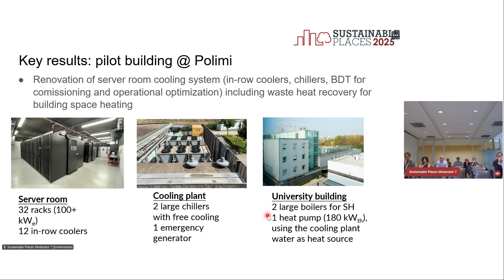Let's see if we can reduce it a little. So, in conclusion, we are optimizing the cooling system, doing different things. We are changing the so-called in-row coolers, a kind of fan coil used to cool down the room, with a higher effectiveness heat exchanger in order to increase the temperature of the chiller loop.